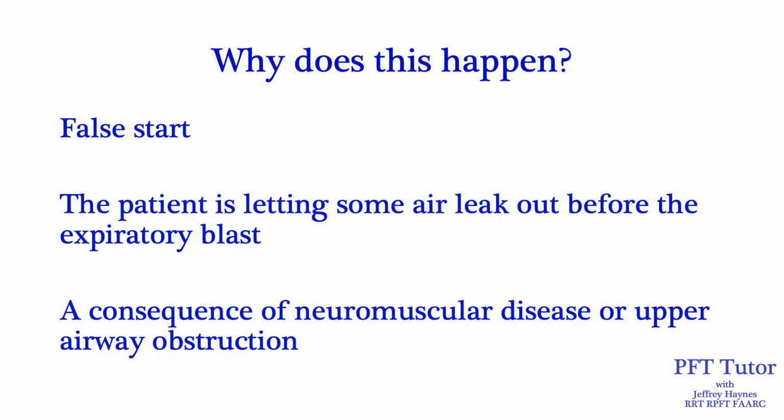Why does this happen? I don't particularly care for the term excessive back extrapolated volume. It doesn't seem to be very descriptive, and it creates a fair amount of confusion. I think a better term would be a false start, similar to football when one of the linemen moves before the ball is hiked to the quarterback.